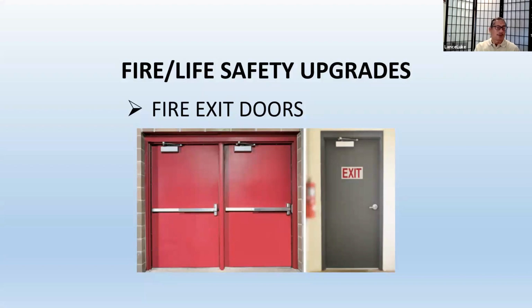Now, here's something to consider. If the door is too hard to open, or it's so corroded or rusty, and maybe through shifting, the door is not fully plumb, and you have to kind of use your body to open the door or close it, that's not a proper working fire door. Okay. So corrosion, rust on the bottom of the door where there's holes and all that, that is not a legal fire door either. Okay, because there's holes in it.